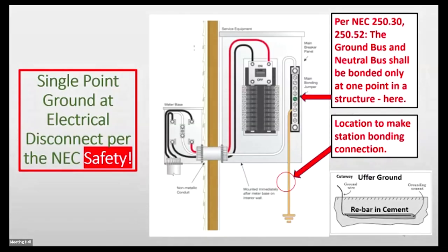Here's what's happening at your house. You have an electric panel with a disconnect in it. The main electrical comes in to the far left, that small box, where the meter is located. Notice there's no ground in the meter box itself. But inside the main disconnect, there's a bar on the far right, and that's where the neutral power connection comes in from the outside—that's the white wire coming in from the meter, all the way from the transformer that feeds your house. That's where there's a ground connection to the outside. That's the only place where the electrical ground and neutral connect in a building—the disconnect, that point only.